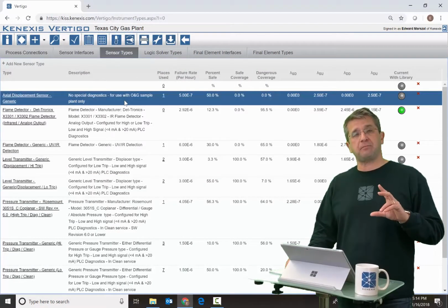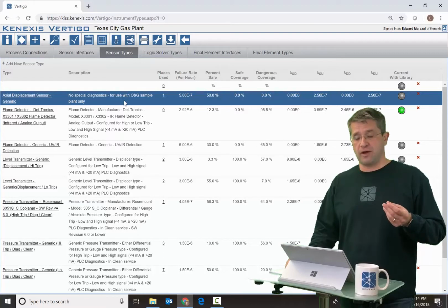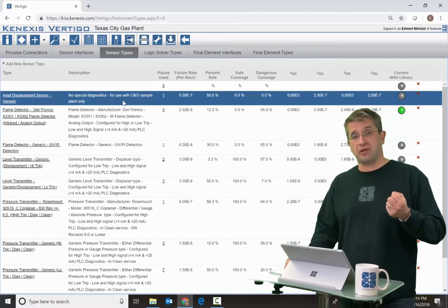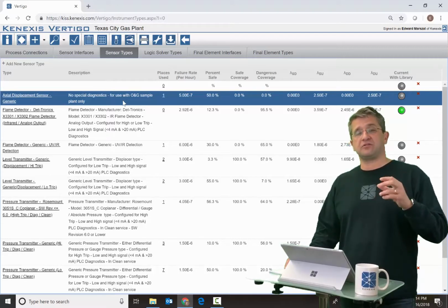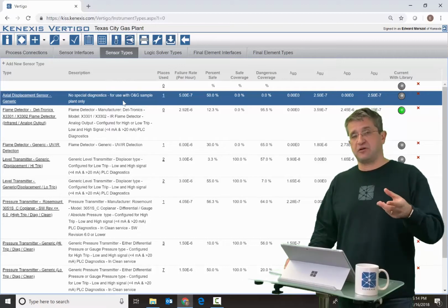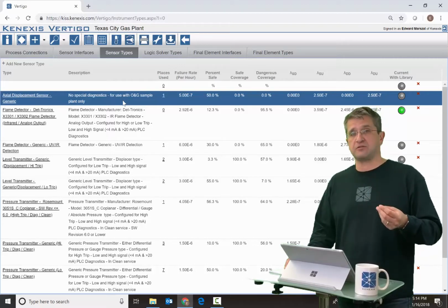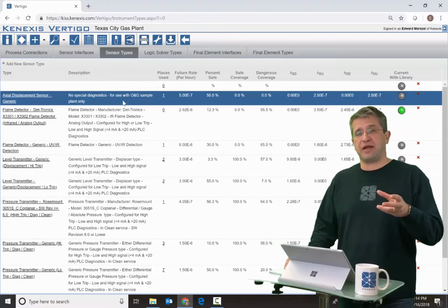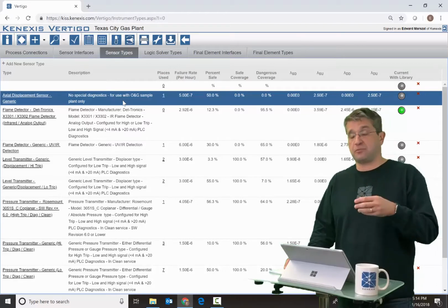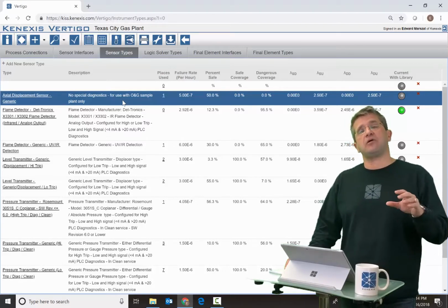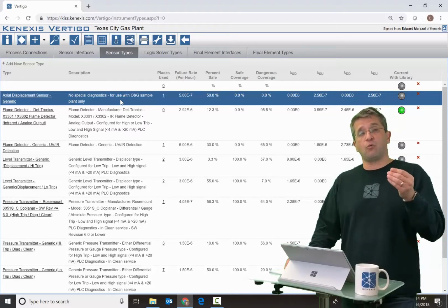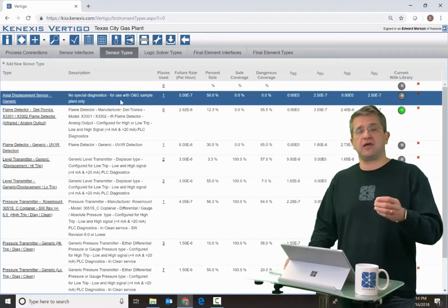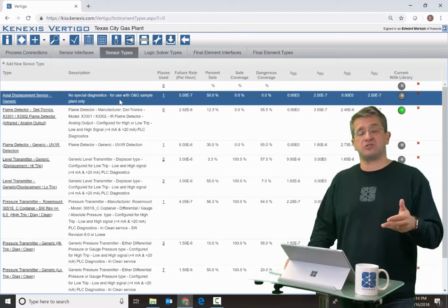And for each different component, we can define it several different ways. We can define our individual components by gathering data from a library. We can custom input the definition of the device for a specific project. We can create a black box model that has direct information about the PFD and the spurious trip rate instead of running calculations. And we can also create a type of black box model where we link the failure rate parameters to fault trees. And we'll get into all of those different methodologies in the coming sections.